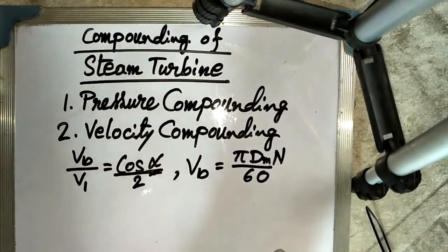Moreover, with a single stage, the velocity of steam at exit is sufficiently high, and there is considerable loss of kinetic energy with the exit steam. To obviate these difficulties, the turbines are compounded or staged. Instead of expanding in a single stage, the steam is made to expand in a number of stages, whereby the turbine speed is reduced while securing the same enthalpy drop of the turbine.